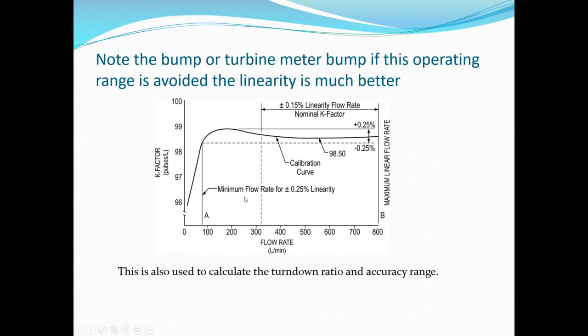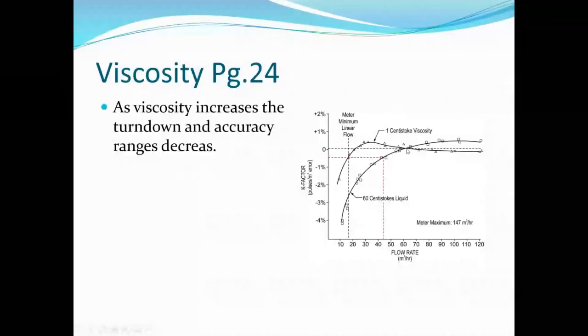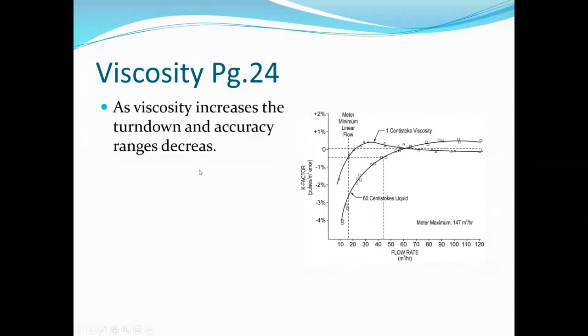Viscosity significantly affects turbine meter performance. As viscosity increases, the turndown ratio decreases and accuracy worsens — the meter has ever-changing accuracy throughout most of its range with only a small area where accuracy is good. So viscosity has a pretty significant negative effect on turbine meters.